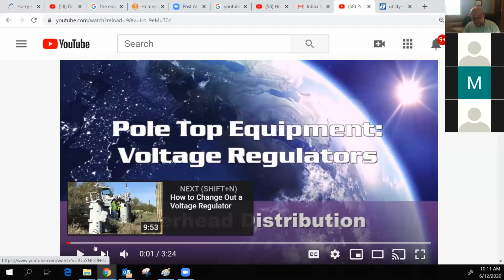We'd have to go to the regulator, check the settings, and raise or lower it. It's supposed to be done automatically, but this man-made equipment isn't perfect, so we'd have to go out there and operate the regulator to get it to the right voltage level for customers at the end of the line. Very important piece of equipment.